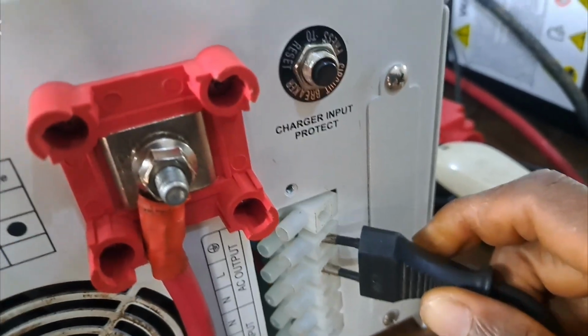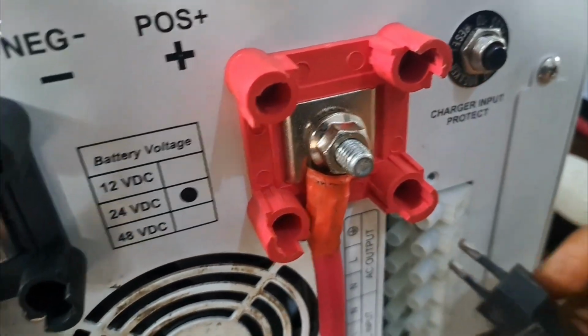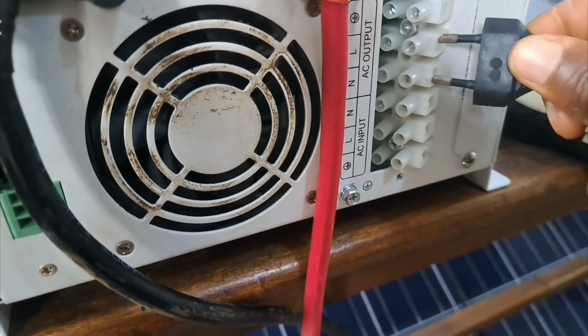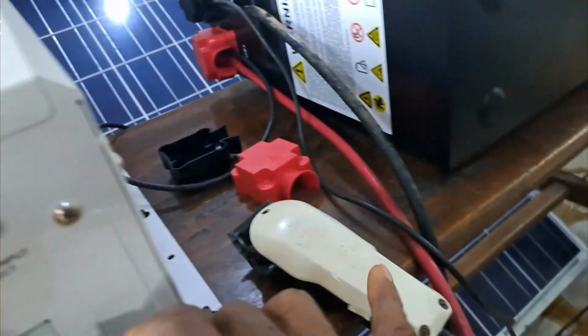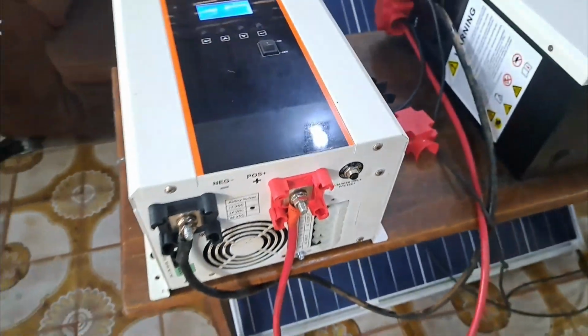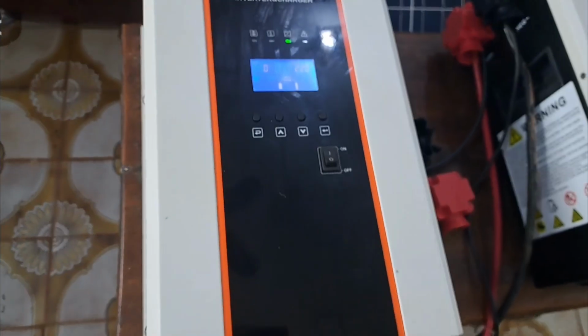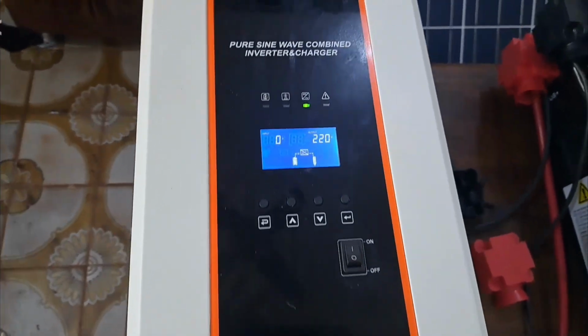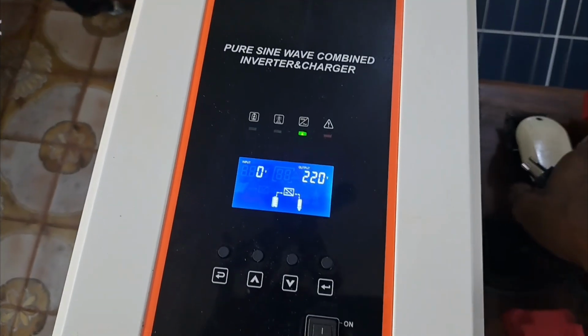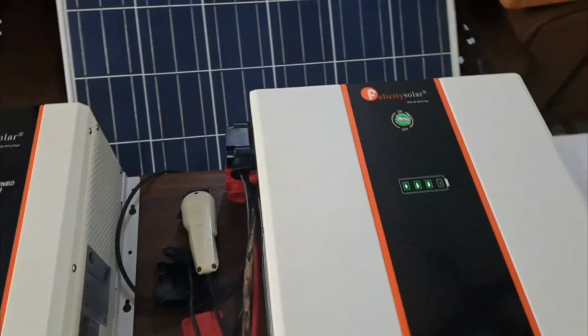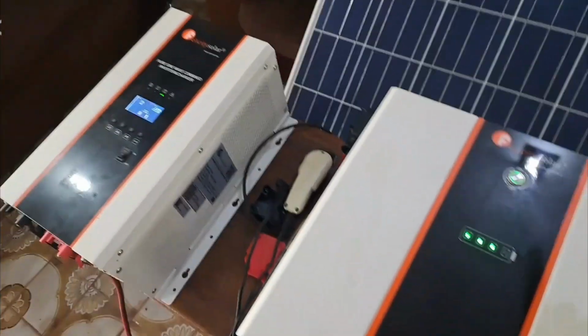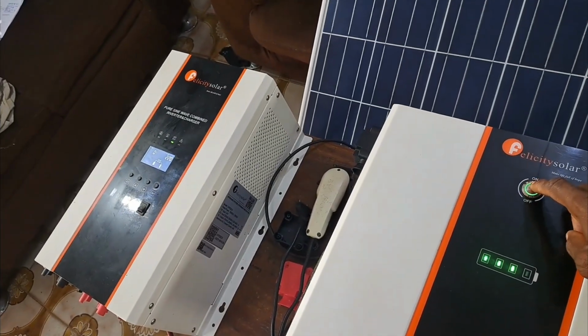If you're one of those persons, make sure that when sizing your system, things go accordingly. As a rule of thumb, the smaller the inverter compared to your battery size, the better, because that way your inverter won't pose any problem or threat to your battery. So if you want to keep your lithium iron phosphate battery safe, make sure you don't oversize your inverter.